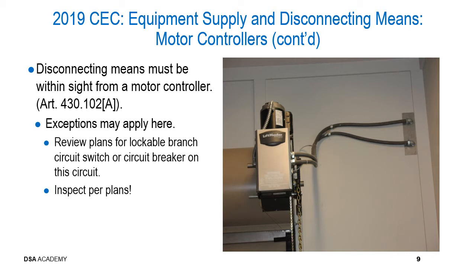And it's important to inspect per the plans. So the point to take from looking at this slide is don't jump to conclusions ever, understanding that the generalized typical requirement for motor controllers and motors is that the disconnect for those is required to be within sight of the motor or the motor controller. Remember, there are exceptions, and the design team may have taken advantage of the fact that there are exceptions, and they've provided the compliant lockable open circuit breaker in the panel that feeds this motor. So again, inspect per the plans.